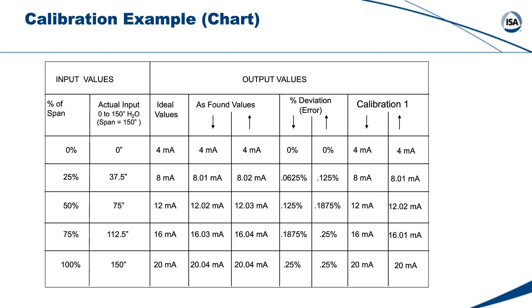is applied. Unfortunately, with analog transmitters, the zero and span adjustments are what we call interactive. That is, adjusting one will affect the other.